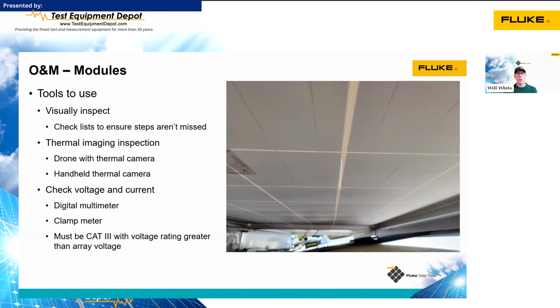Now, this photo here is a picture of the backside of a module. We've got some cracking in that back sheet. You can see the line right in the middle, where between the two cells you can actually see right through the back sheet and right through the front glass there. So with an obvious visual inspection, that's obviously damage there. Also, I see a bunch of hanging wires down here. Hanging wires always drive me crazy because those are just going to get damaged over time. So that would be a red flag for me.